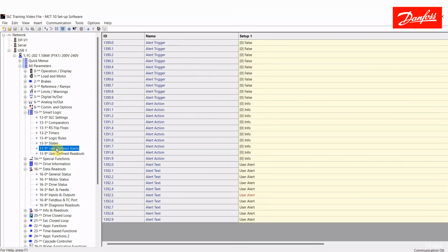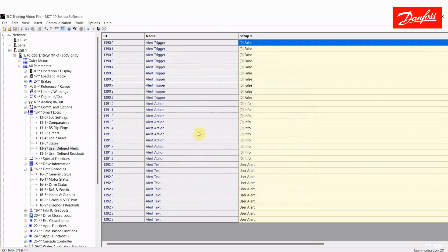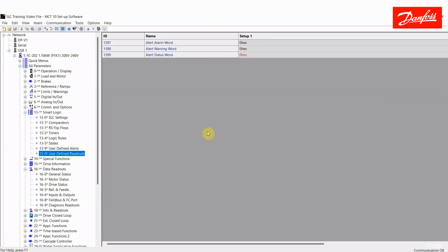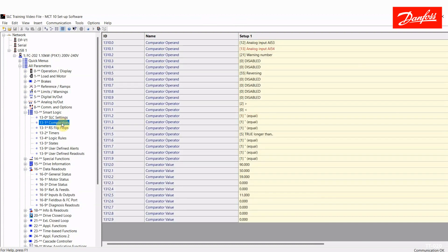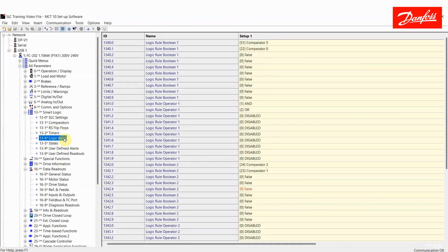User defined alerts. You can create customizable triggers to create a custom message. So that's what user defined alerts are. And user defined readouts. Here we get a hexadecimal representation of customizable alarm words and status words. So that's for reading through serial comms and such. So those are the main parameter groups within the smart logic controller. I've already demonstrated how to use comparators and logic rules and attach them to physical outputs.